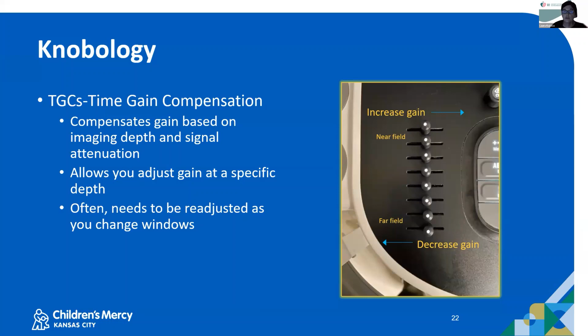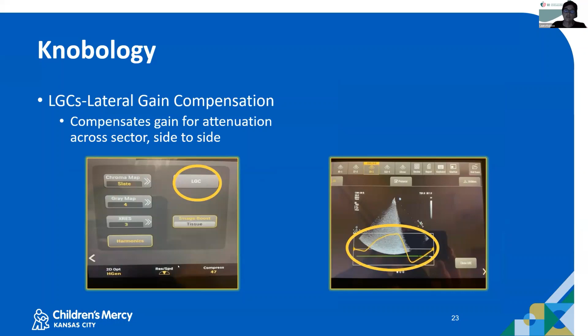You also have lateral gain compensation, and this compensates for gain attenuation across the sector side to side. So what you're going to do is hit the touch screen, touch this button here on the Philips. You have this horizontal line. You're going to take your finger and drag it up to add gain to enhance whatever part of the sector needs improvement.